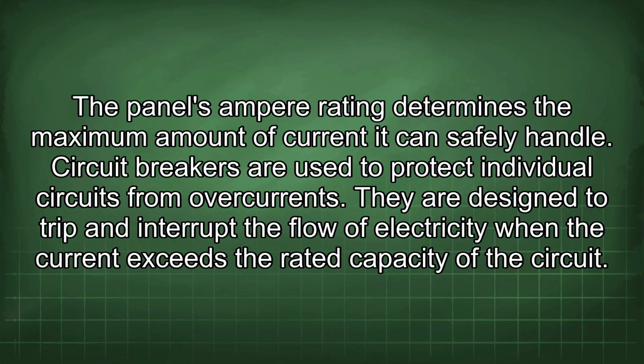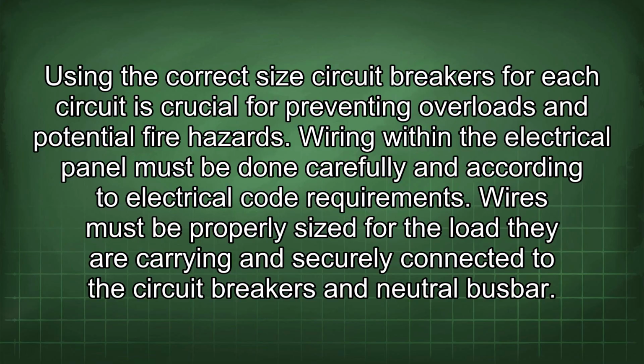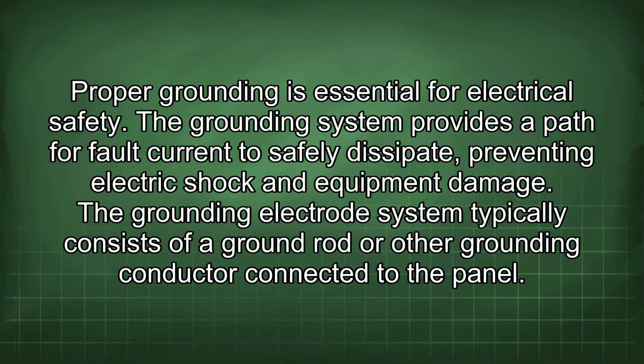Circuit breakers are used to protect individual circuits from overcurrents. They are designed to trip and interrupt the flow of electricity when the current exceeds the rated capacity of the circuit. Using the correct size circuit breakers for each circuit is crucial for preventing overloads and potential fire hazards. Wiring within the electrical panel must be done carefully and according to electrical code requirements. Wires must be properly sized for the load they are carrying and securely connected to the circuit breakers and neutral busbar. Proper grounding is essential for electrical safety.